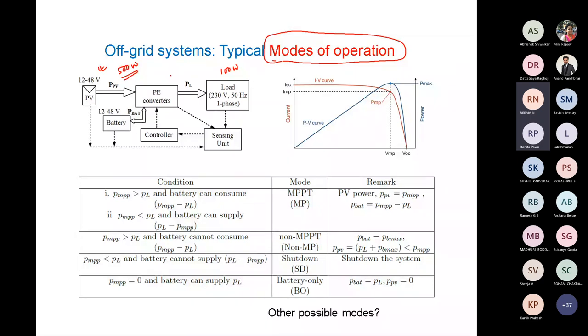Based on this condition, we need to define some modes of operation. First mode: PMPP is the maximum power available from solar. If PMPP is greater than load demand, that means I have extra power and I can charge the battery, no problem, as long as the battery is not fully charged. So we'll operate in MPPT mode.